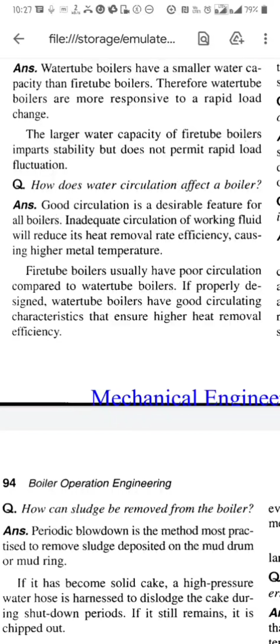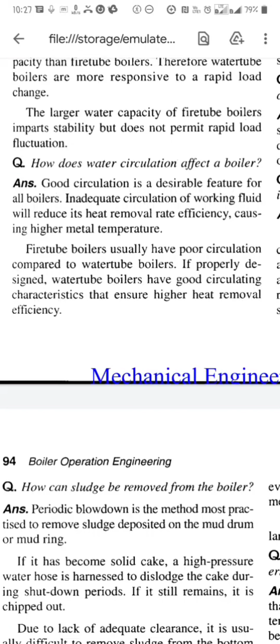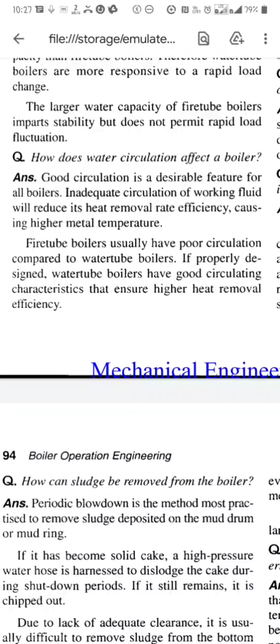Question: how does water circulation affect a boiler? Answer: good circulation is a desirable feature for all boilers. Inadequate circulation of working fluid will reduce its heat removal rate efficiency, causing higher metal temperature. Fire tube boilers usually have poor circulation compared to water tube boilers. If properly designed, water tube boilers have good circulating characteristics that ensure higher heat removal efficiency.